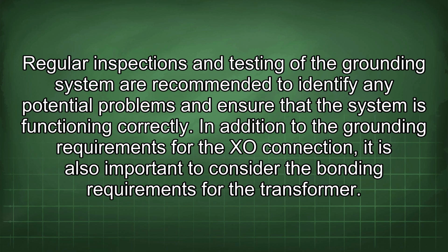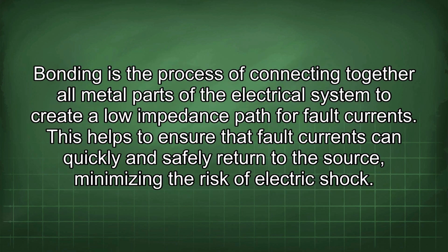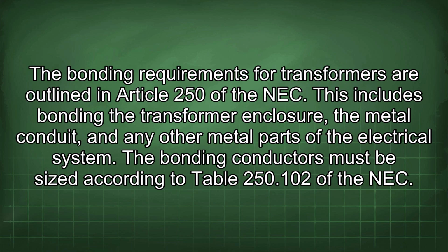In addition to the grounding requirements for the XO connection, it is also important to consider the bonding requirements for the transformer. Bonding is the process of connecting together all metal parts of the electrical system to create a low impedance path for fault currents. This helps to ensure that fault currents can quickly and safely return to the source, minimizing the risk of electric shock. The bonding requirements for transformers are outlined in Article 250 of the NEC. This includes bonding the transformer enclosure, the metal conduit, and any other metal parts of the electrical system.